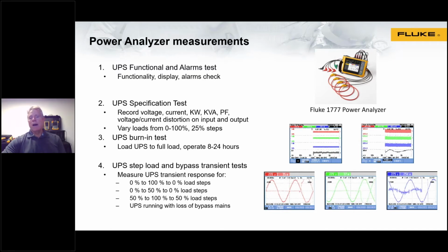So the first one on A phase and B phase, or L1 and L2 I'll use, you would have 100% load, then 0 on L3. The second step would be 0% load on L1 and L2, and then 100% load on L3. The third step would be 100% load on L1, 50% load on L2, 100% load on L3. And then for the fourth and final step, 50% load on L1, L2 would have 100% load and then 50%. In that way, you're fully exercising the specification based on both balanced and unbalanced loads.